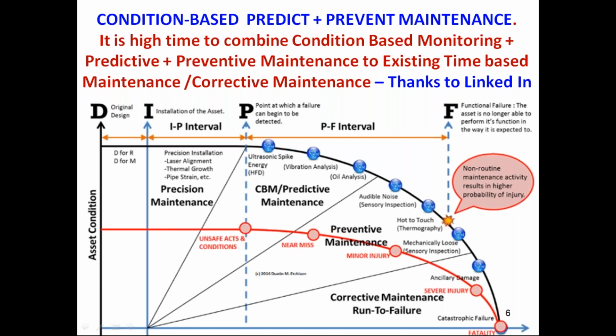So once we take up predictive maintenance, that will give an indication from the point of first failure to the failure of the equipment. Definitely the predictive maintenance will overtake the preventive maintenance and it will not allow the machine or the process to go down because of breakdown.